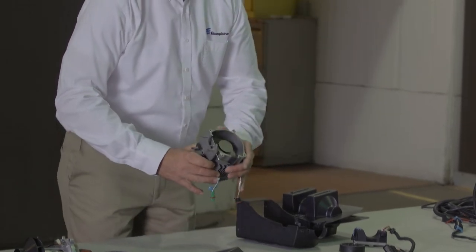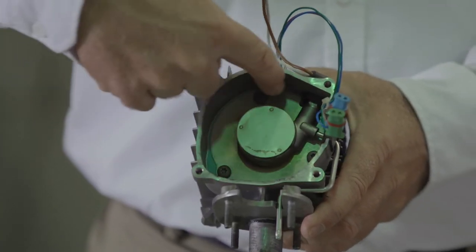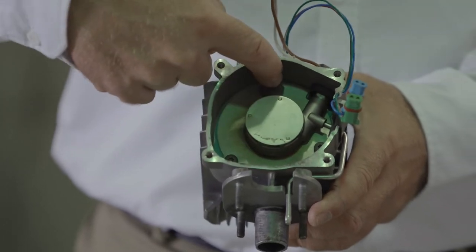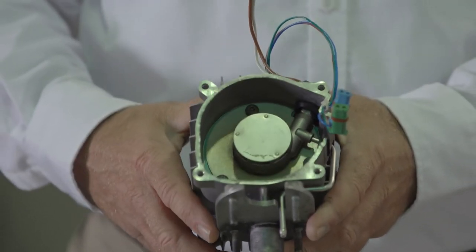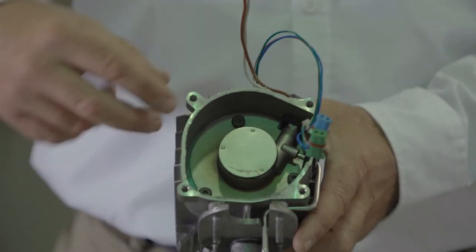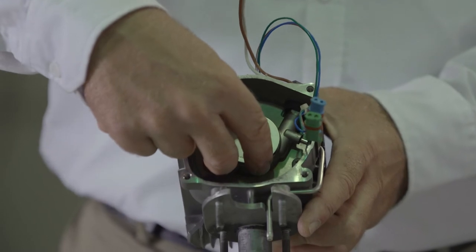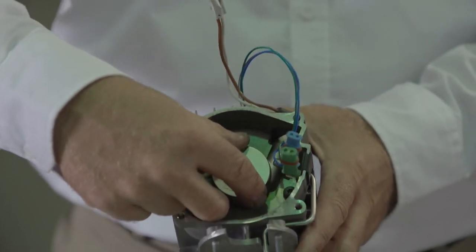Just as a side note, you're now looking at the burner chamber and you'll notice the green thermal insulator under the burner chamber. It will be cracked. That is normal and not a concern. If you remove the burner chamber, you must have a gasket to replace it with or a thermal insulator to replace it with.